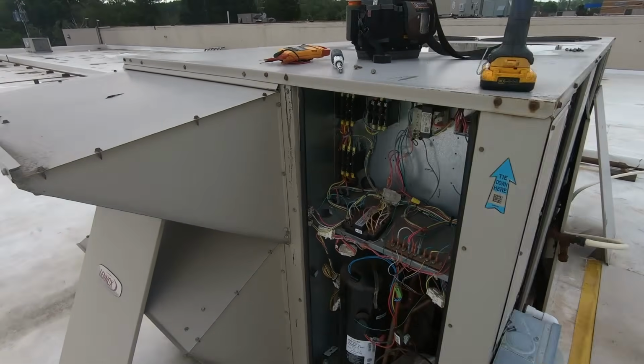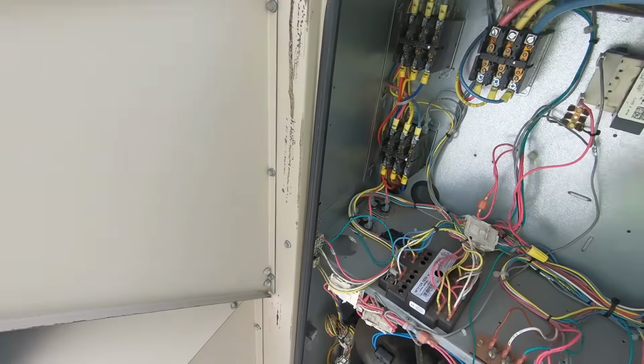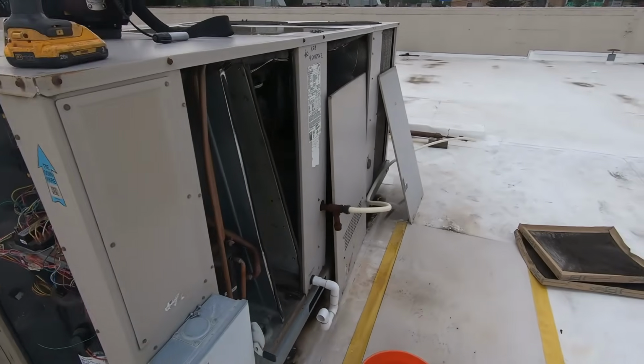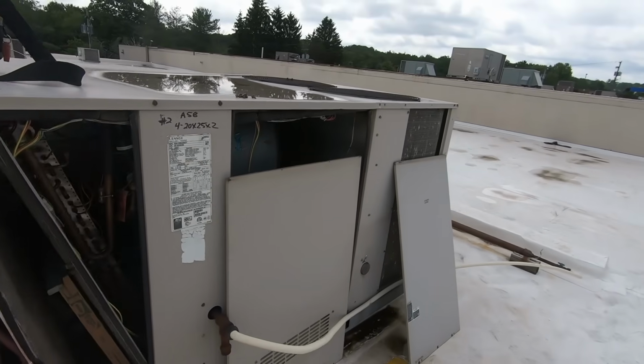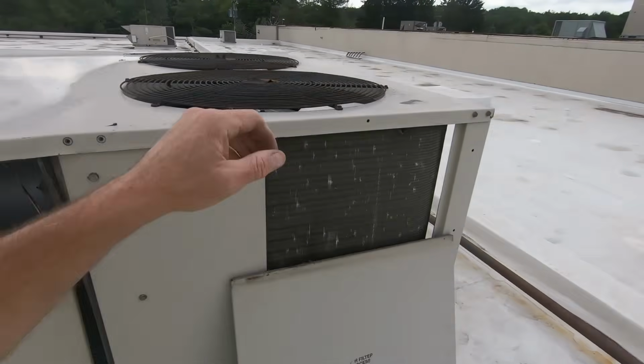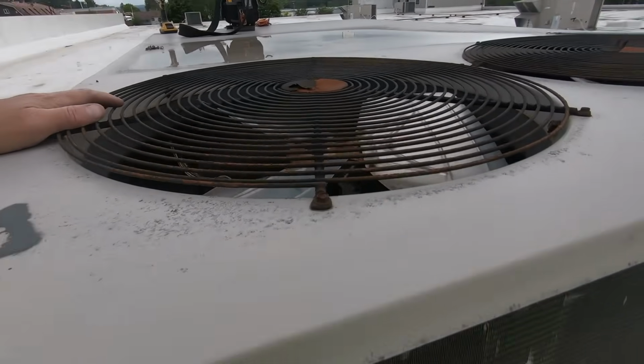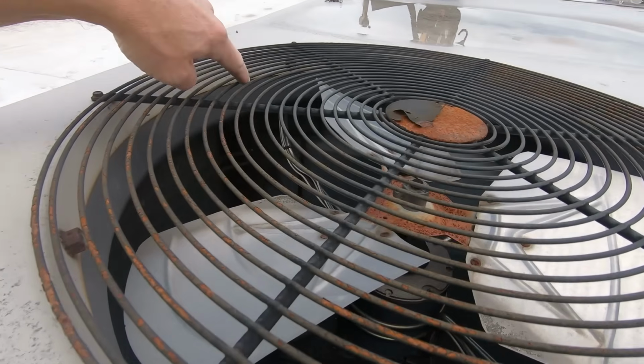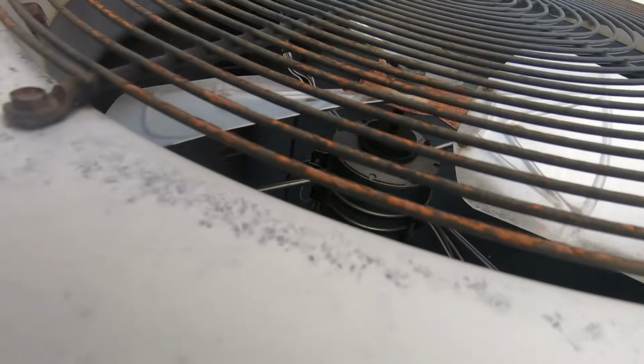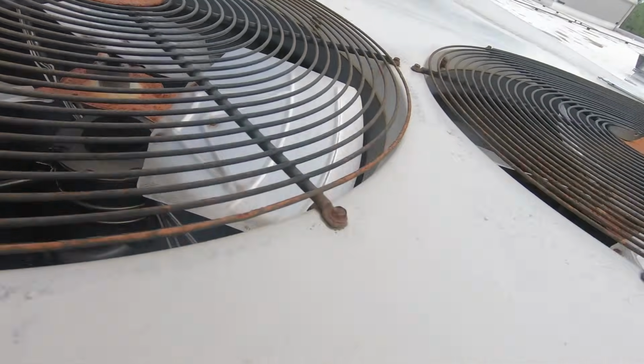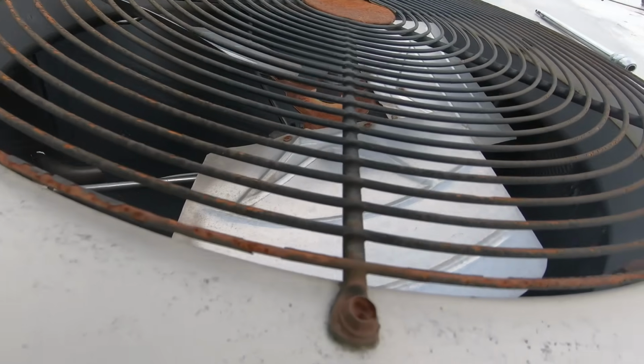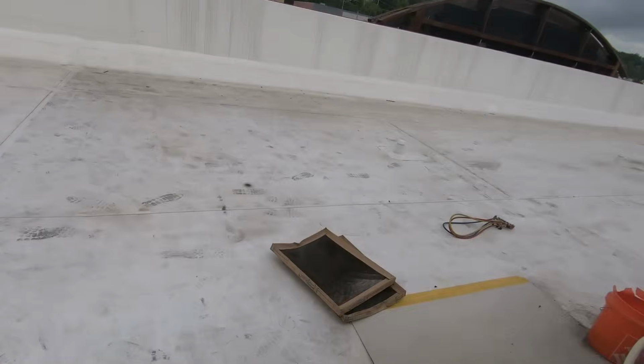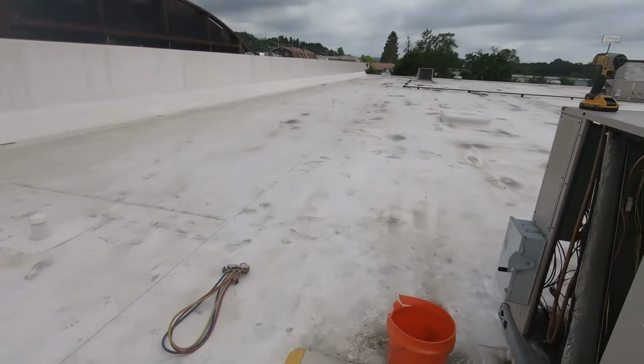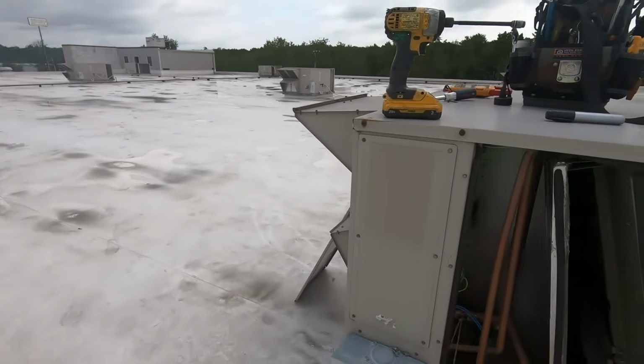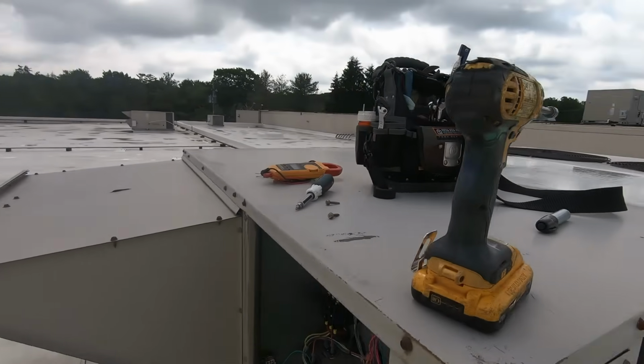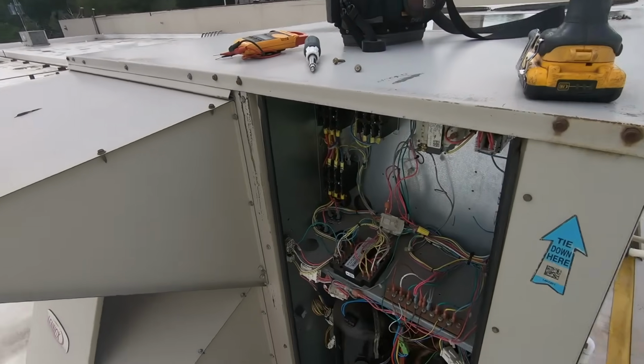Okay, well, contactors are starting to pit a little bit. I'm going to write them up. Compressors both test good electrically. Blower motor tests good electrically. Fan motors test good. Nothing shorted to ground. From what I can see here, the wiring all looks decent. So I'm going to go find the breaker, confirm that it's tripped and not off. I do want to check and see if we have refrigerant in both of these circuits before I go down.